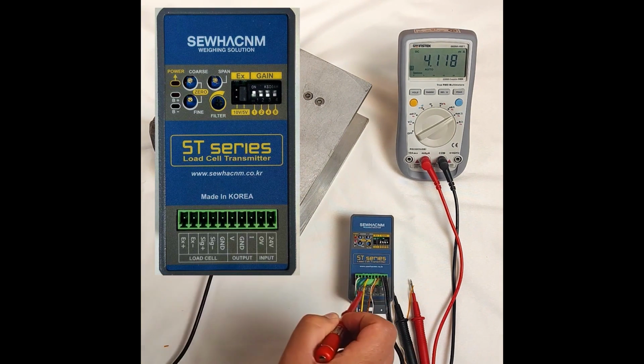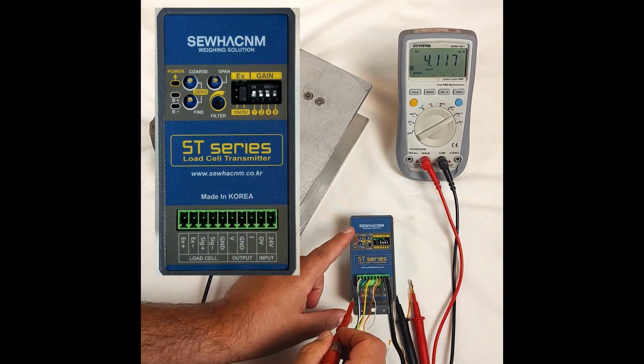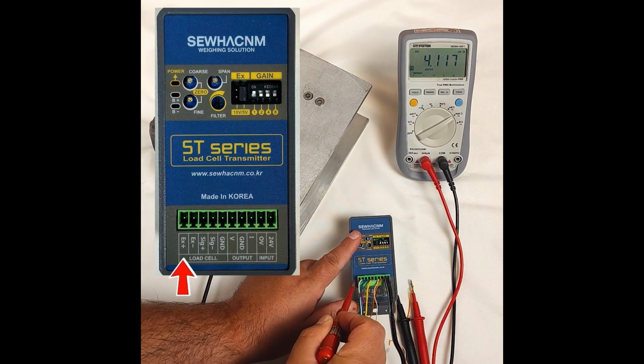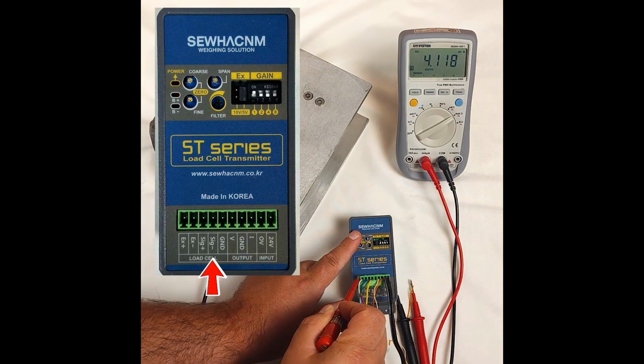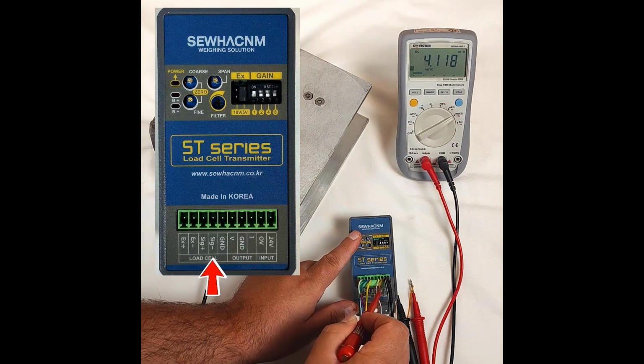Since our load cell is from the brand SEWHA, the wiring is as follows. Positive excitation is connected to the red wire. Negative excitation is the white wire. Positive signal is the green wire, and negative signal is the blue wire.